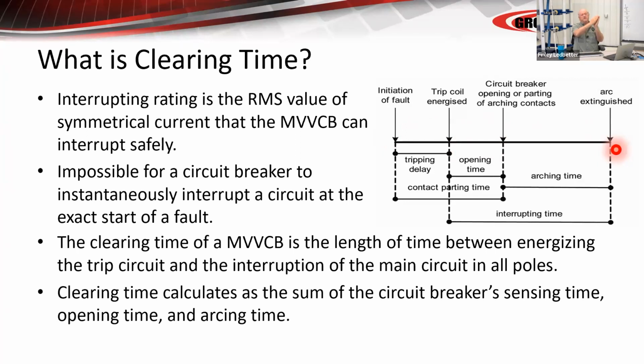That's parting time. Then the contacts have to move across an arc. It has to bow the arc, and the arc has to be broken up in the arc chamber and extinguished to interrupt the circuit. And that total amount of clearing time is what's required for your arc flash study to be valid. So you have an arc flash boundary that's based on optimal conditions and things running at proper speed and velocity. If they don't, as time extends, this arc flash boundary extends as well.